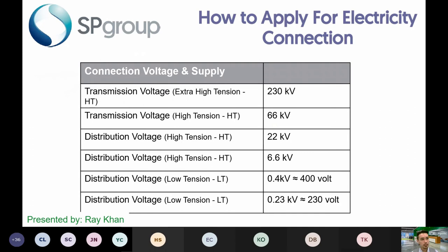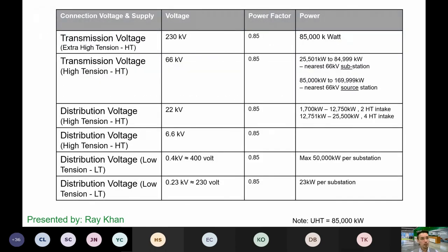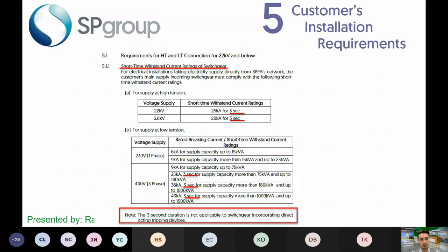So these are the different steps. They start with the extra high tension, 230 kV, and then it goes downwards from 66 kV right down to 22 kV and right down to LT. So for LT, we are talking about 400 volt to 230 volt. Right, so a key point to take into consideration that is written in there is the power factor, for the different steps, all at 0.85. It also talks about the short time withstand current rating for the switchgear. So I think the key emphasis in here is the 25 kA 3 second for the short time withstand current rating.